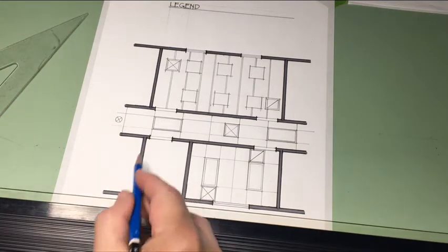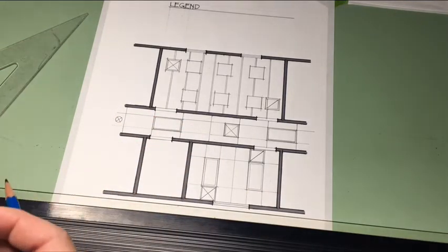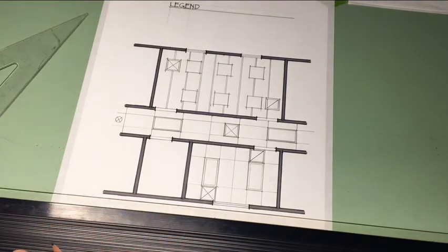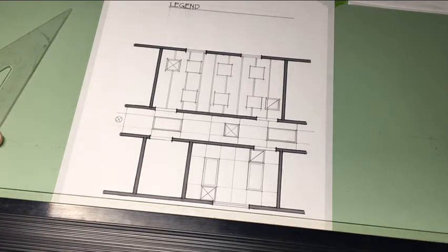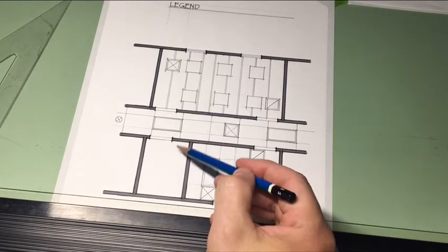So then the last one is this little restroom that I have right here, and it's going to be a gypsum board ceiling. But I'm going to follow the same process as what I did for the open ceiling. I'm going to show the light, and then I'm going to show a supply air, and then we're going to show a fan, an exhaust fan, because we're not going to take that air back to the air handler and then spread it throughout the entire building. We're going to take the air from the bathroom and exhaust it out through the roof or to the exterior. So you need to know a little bit about what your layout is below, even though I haven't drawn it.